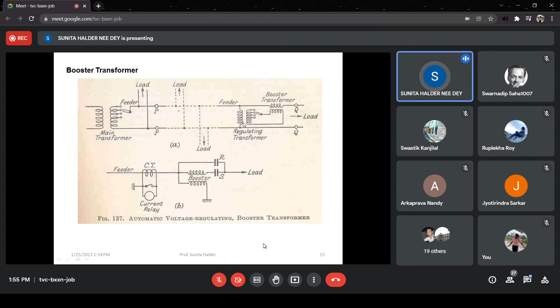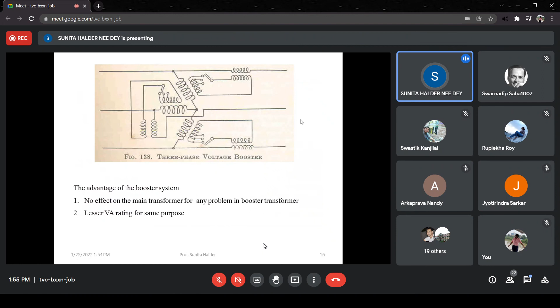A booster transformer is for local, instantaneous use, not for regular use. Because using a booster transformer or regulating transformer, we are actually using more inductive reactive power, and voltage drop is due to inductive reactive power. So using a device which draws inductive reactive power, we cannot compensate voltage drop in a better way. That's why its application is always limited. So this is the three-phase type concept.